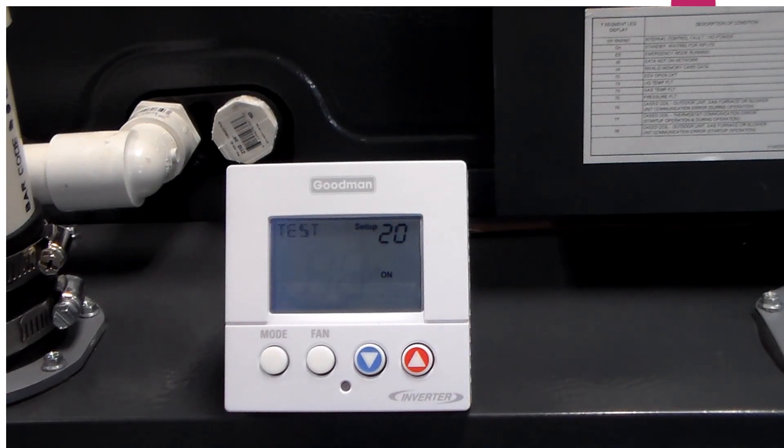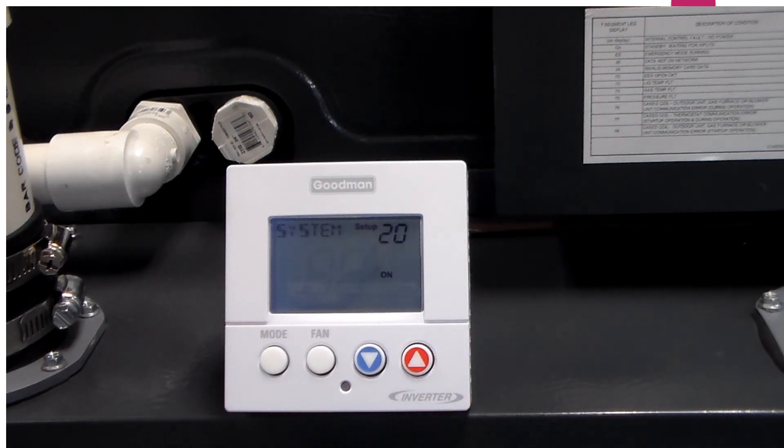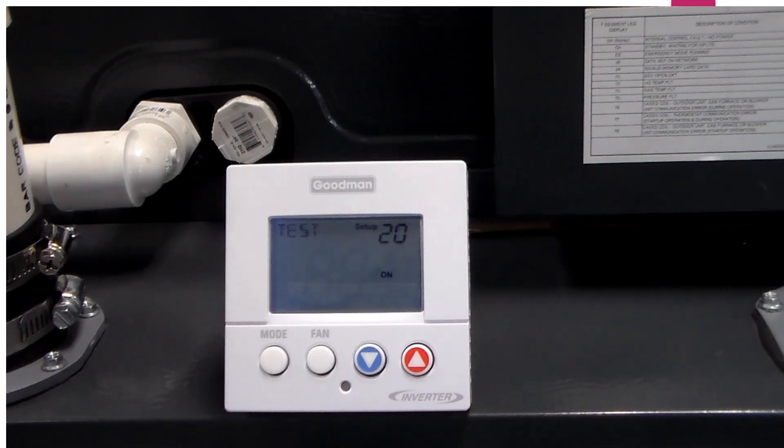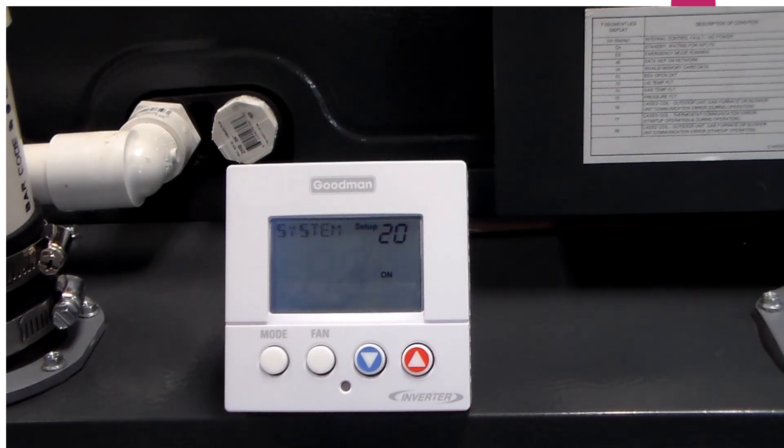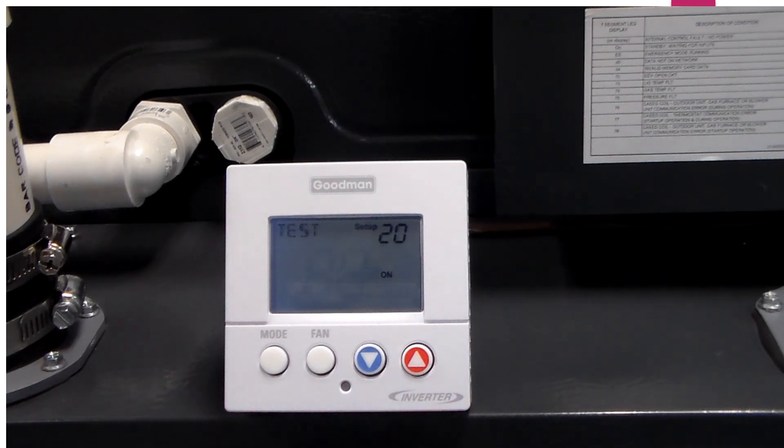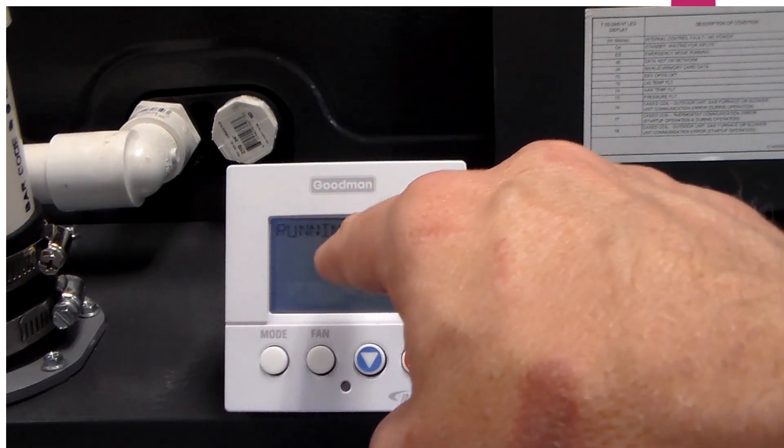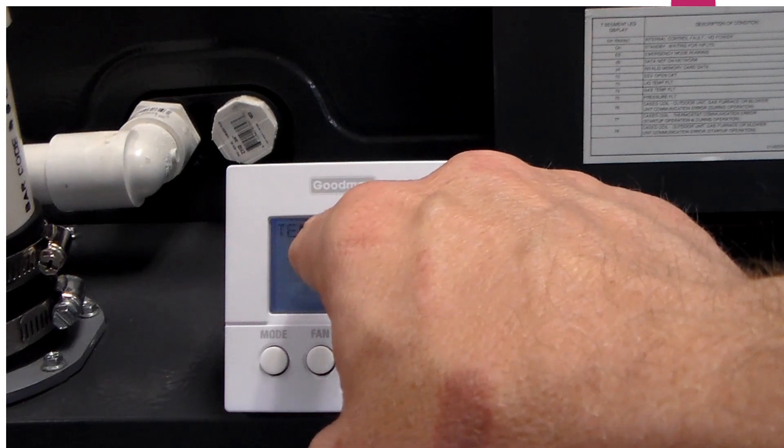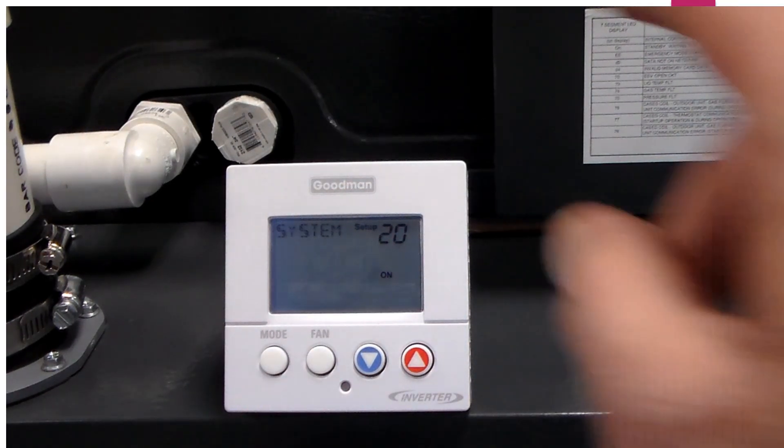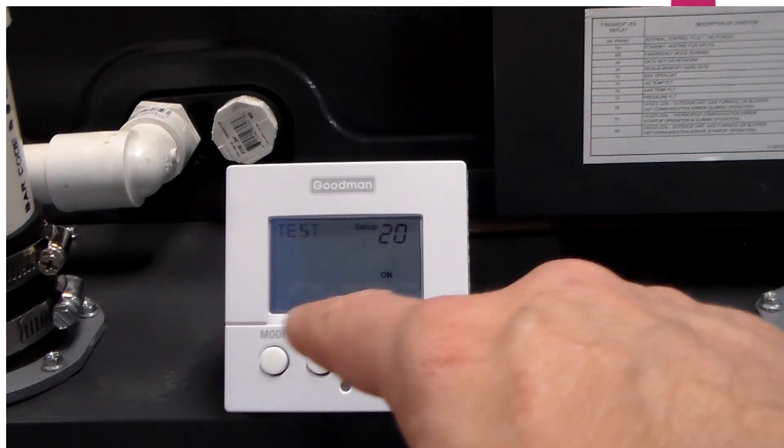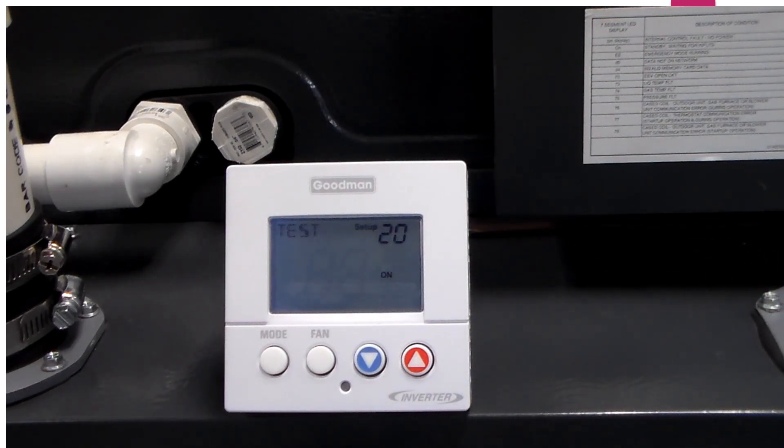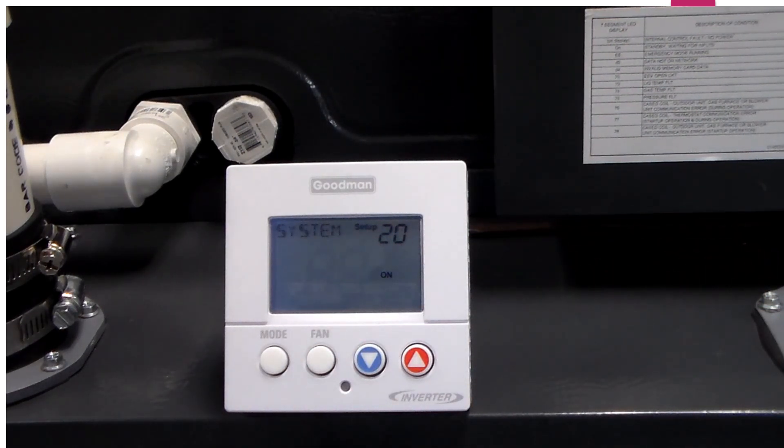Test mode is always done in the cooling cycle. It will run this entire system from zero capacity all the way up to full capacity, and it will test out all the system components. When it's finished, it will tell you test mode done. Right now, it says system test running. You can go ahead and hit mode and return back to the home screen once you are finished.